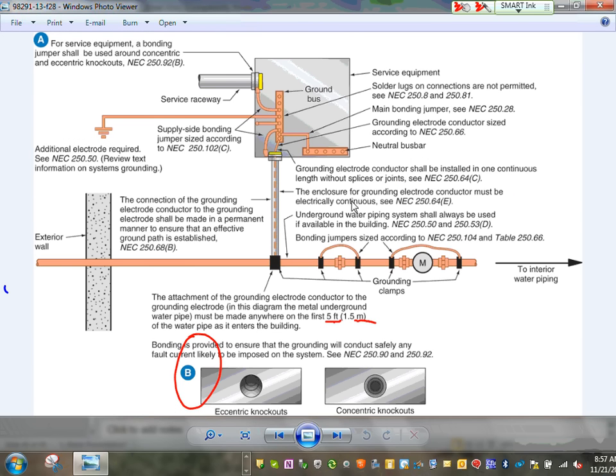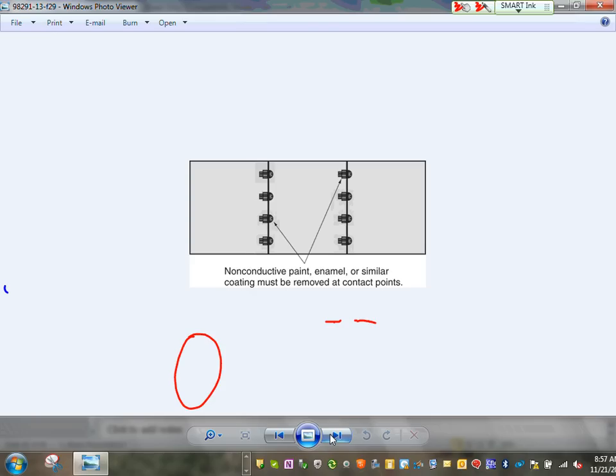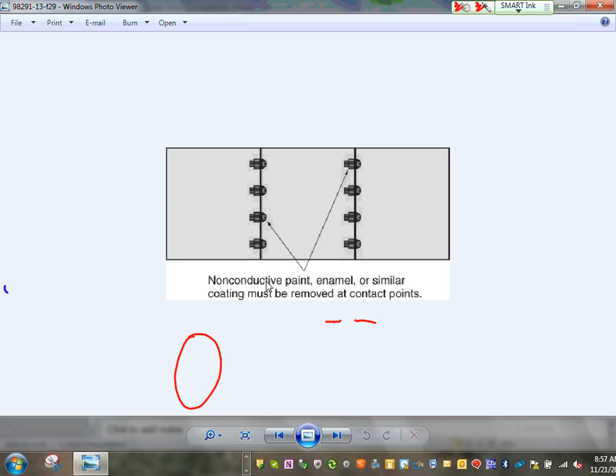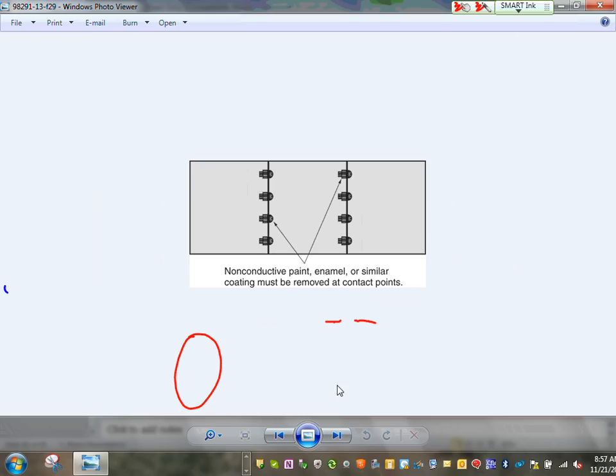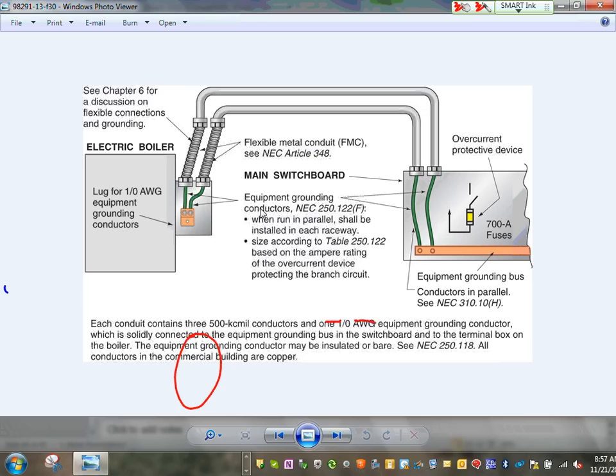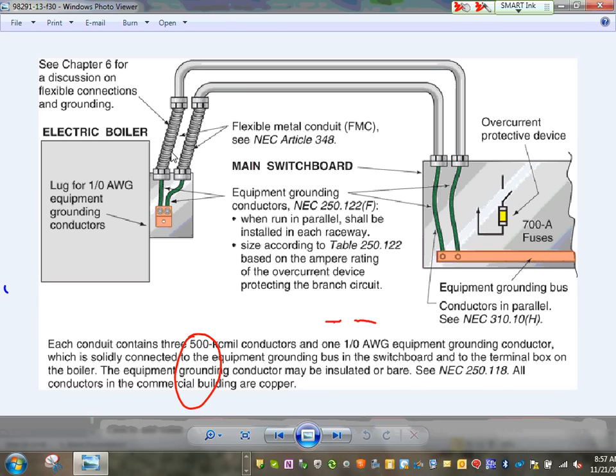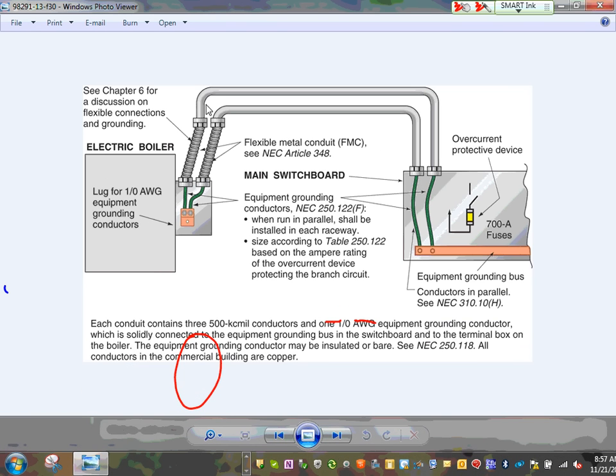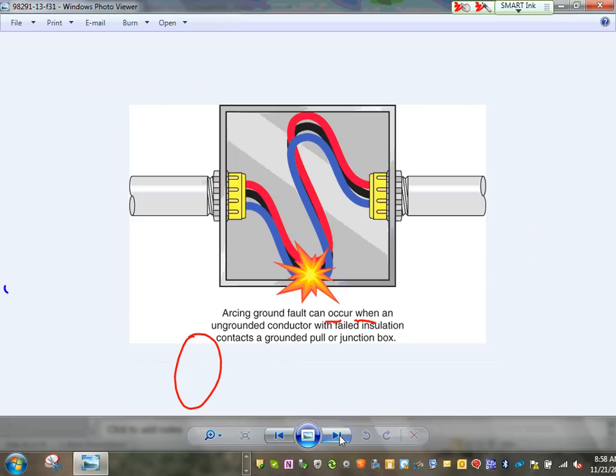You have to have a bonding bushing and bond the conduits. You guys, I know you're not an electrician. We emphasize this a lot for the electricians, but when you become a project manager, it's really nice to know all this stuff too. Okay, when you're doing bonding, non-conductive paint has to be removed so you can have good connections. If you have a flexible like this, you have to also bond around the flexible, because flexible is not meant as an equipment grounding or bonding conductor.